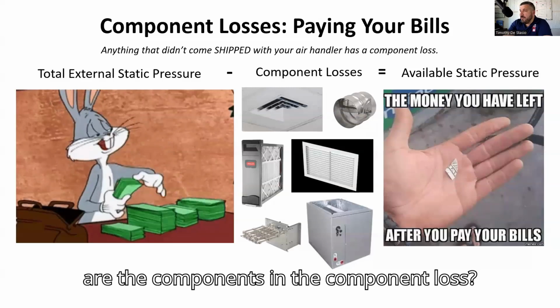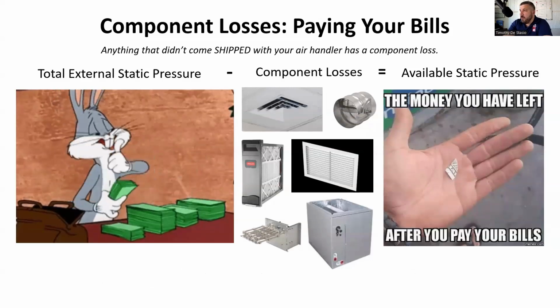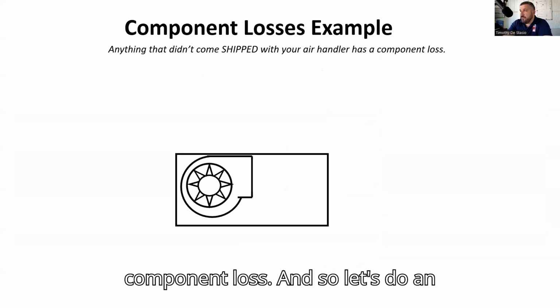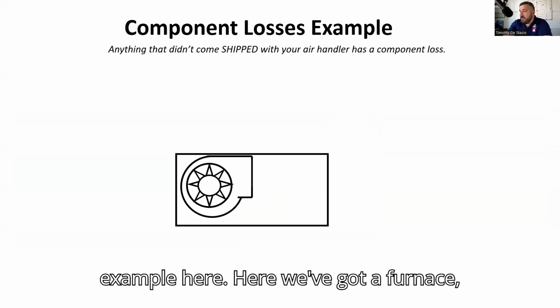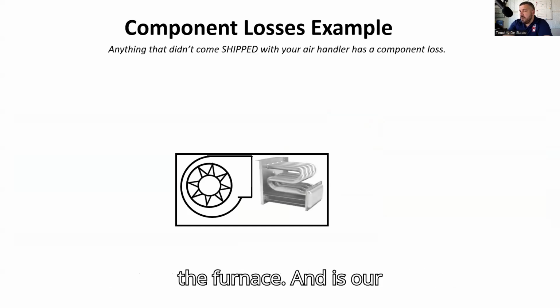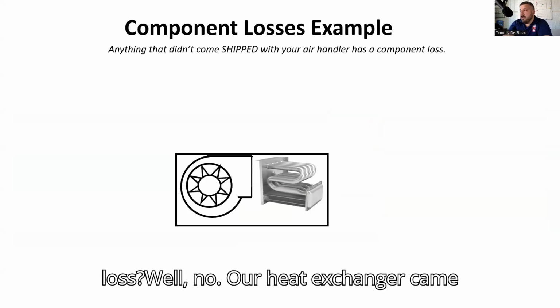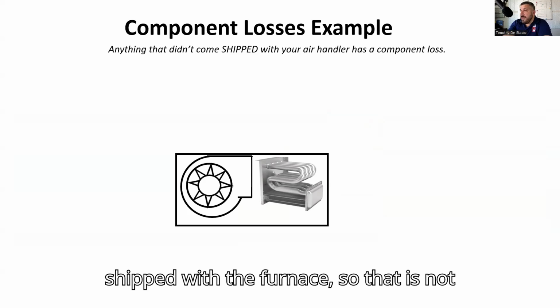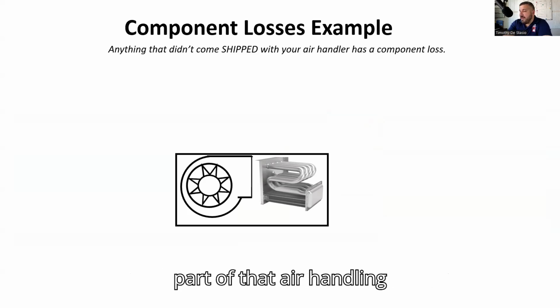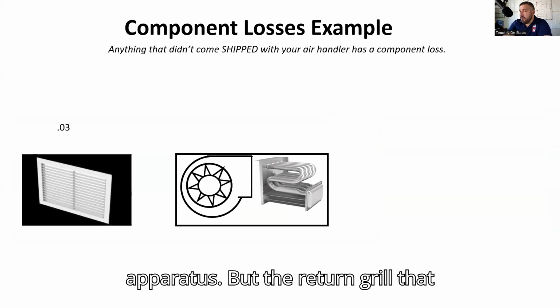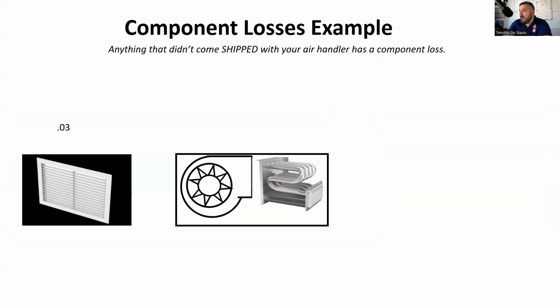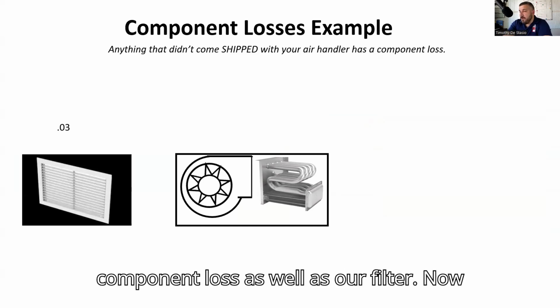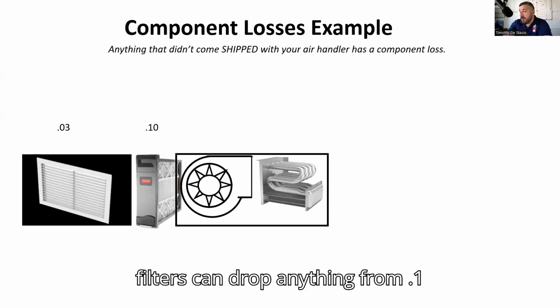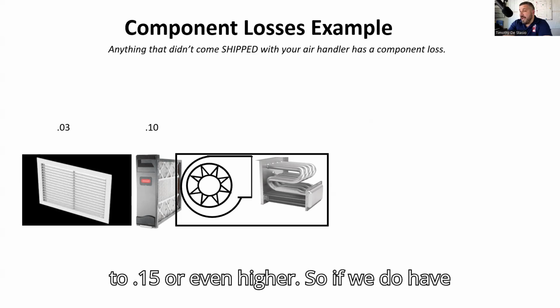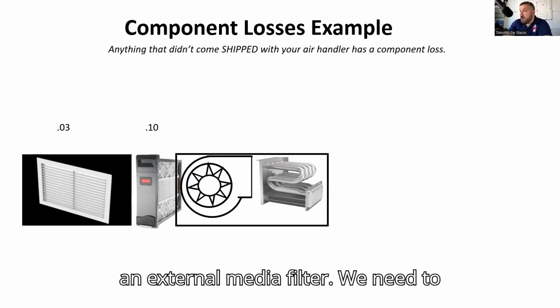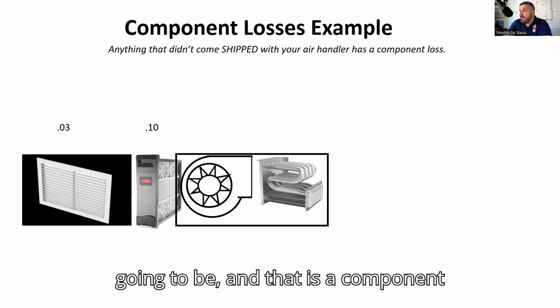And so, what are the components in the component loss? It's anything that didn't come shipped with your air handler that has a component loss. And so let's do an example here. Here we've got a furnace, we've got a blower on the return side of the furnace, and is our heat exchanger considered a component loss? Well, no. Our heat exchanger came shipped with the furnace, so that is not considered a component loss. That's part of that air handling apparatus. But the return grill that Manual D details us to deduct 0.03 inches static pressure from, that is a component loss, as well as our filter. Now, filters can drop anything from 0.1 to 0.15 or even higher. So if we do have an external media filter, we need to figure out what that pressure drop is going to be, and that is a component loss.